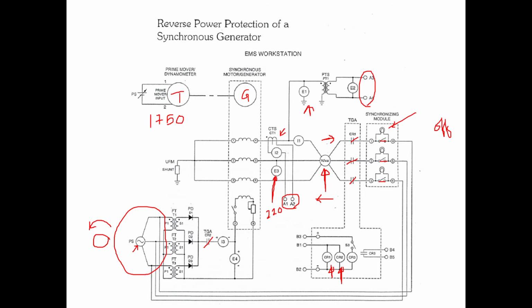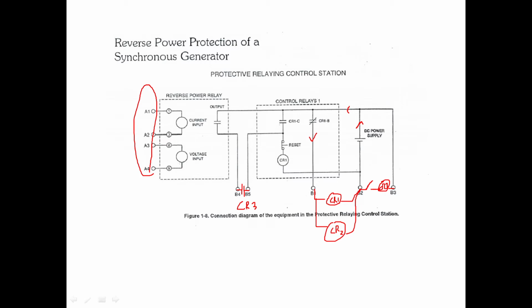When the direction starts to reverse, this contact would be closed. If this contact is closed, you can see a red light here. This red light indicates that the relay has sensed the fault, but it will not take any control action because this contact is still open. So what I want you to do now is close the CR3 switch manually. That means this contact will close.